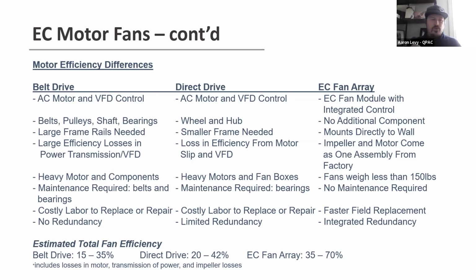So there's no additional heat load, no eddy currents, no destructive phases going through that fan. There are no additional wheels, pulleys, or hubs that you have to do. Mainly, like with the direct drive, you're buying a motor from Baldor, Marathon or something like that, a wheel from one manufacturer, a hub from another, and all of that stuff is not balanced as a whole. Whereas the EC fan is built as one complete piece. The motor, the impeller, all that stuff's mounted together and then balanced from the factory. Therefore, it can be rigidly mounted via AMCA. So there's no additional vibration rails, there's no cork insulation, no spring isolators, and no other losses that you would get from that.